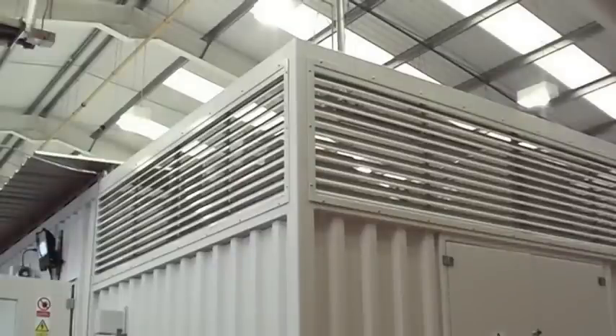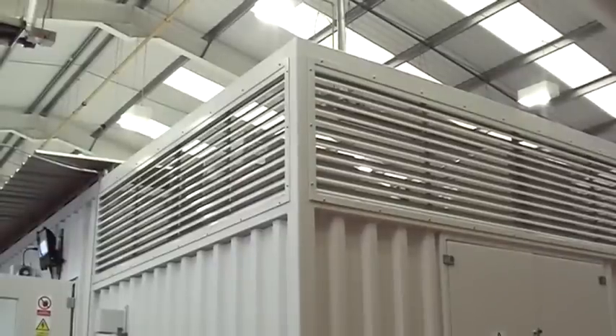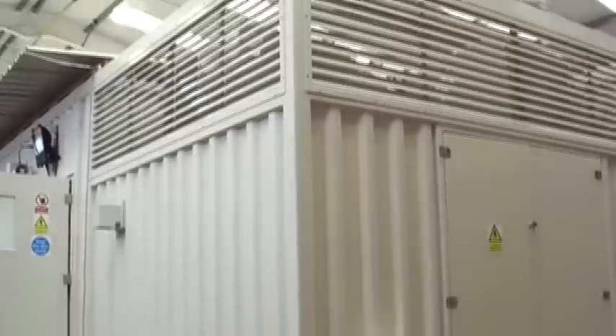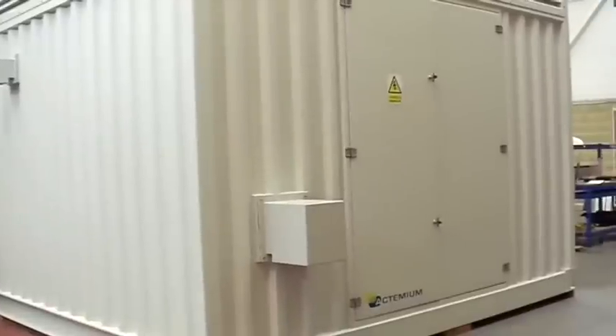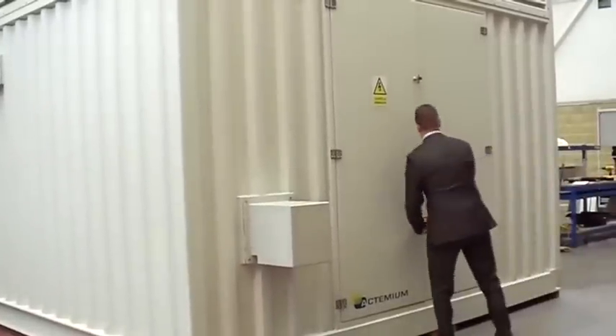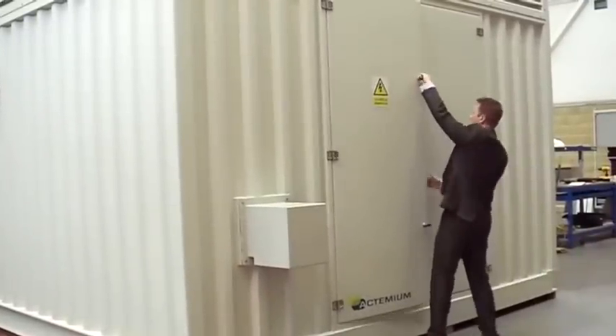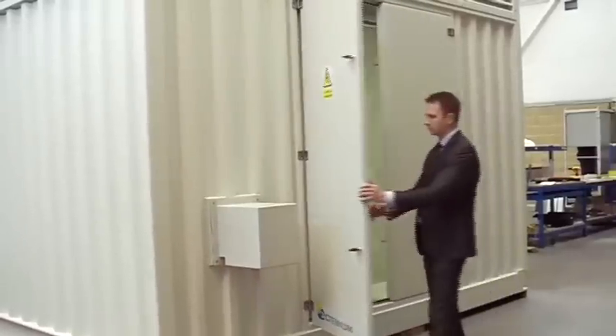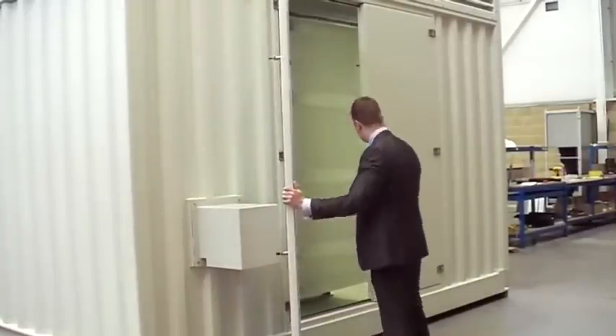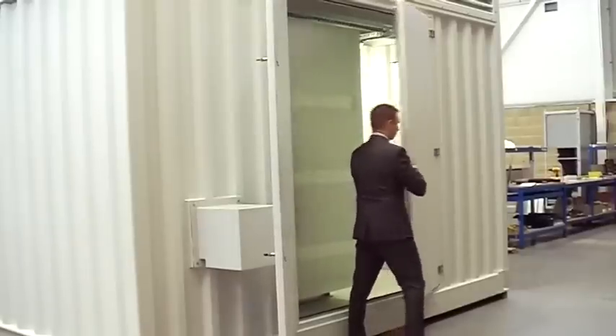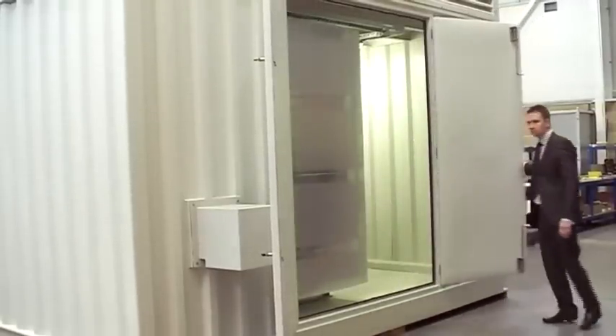The internal environment is created using a dual-redundant HVAC system and is capable of maintaining a room temperature of +19 to +30 degrees C, with an external temperature of +5 to +50. The redundant air handling units are located in the adjacent HVAC plant room, with the corresponding condenser units located on the roof at the end of the module and hidden behind the louver panels.